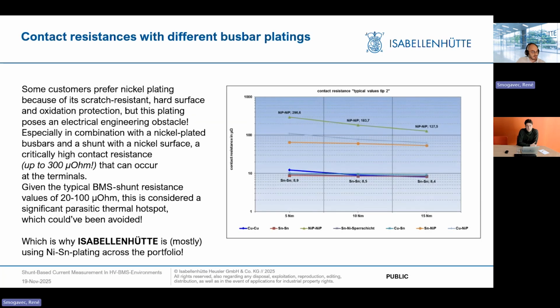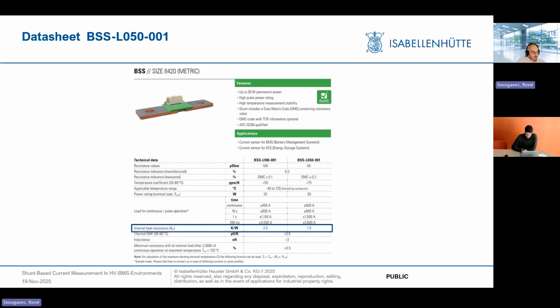Also important is that contact resistances can be very high. So we're talking about 25 to 100 microohm. Some customers like to use nickel plating. We really try to not use nickel plating because of the hotspots that can occur on the terminal itself. So we really emphasize using nickel tin, also for the preservation of both surfaces. And that's why all or most components are nickel tin plated. The RTHI is listed here in the datasheet as well. So 2.0 or 1.5 Kelvin per watt is generated as the hotspot.